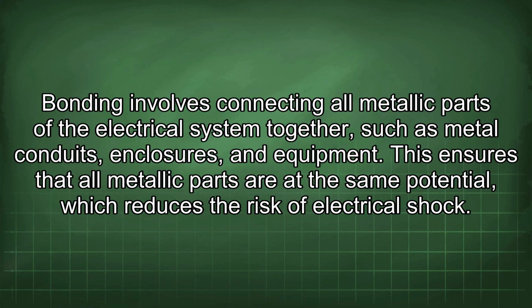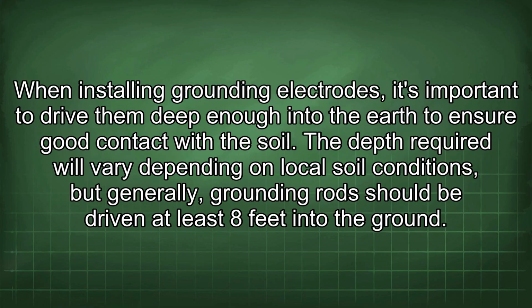Bonding involves connecting all metallic parts of the electrical system together, such as metal conduits, enclosures, and equipment. This ensures that all metallic parts are at the same potential, which reduces the risk of electrical shock. When installing grounding electrodes, it's important to drive them deep enough into the earth to ensure good contact with the soil. The depth required will vary depending on local soil conditions, but generally, grounding rods should be driven at least 8 feet into the ground.